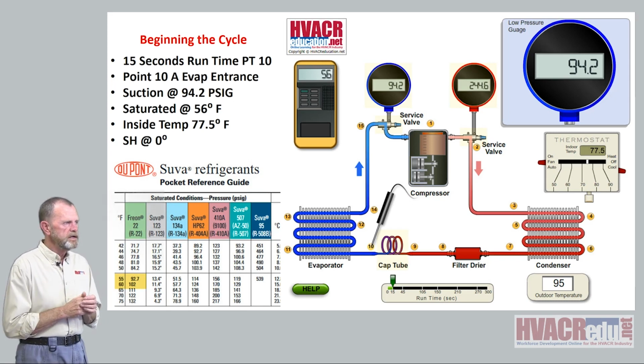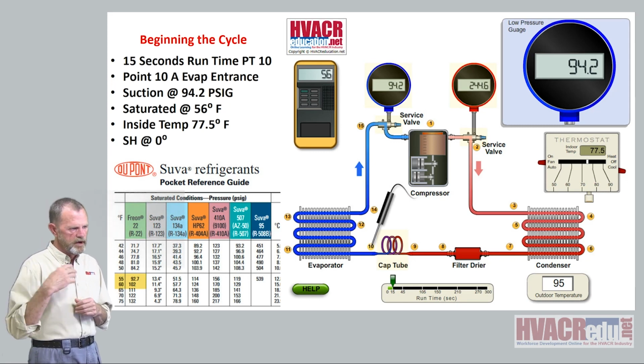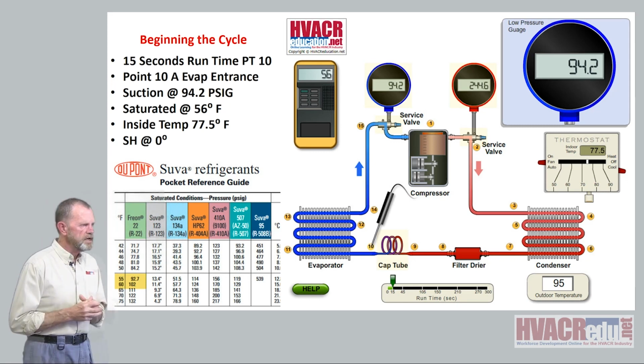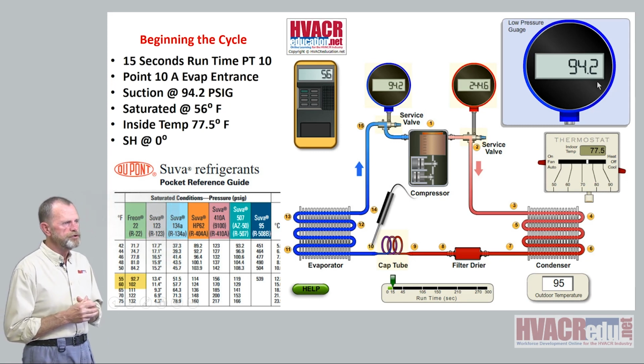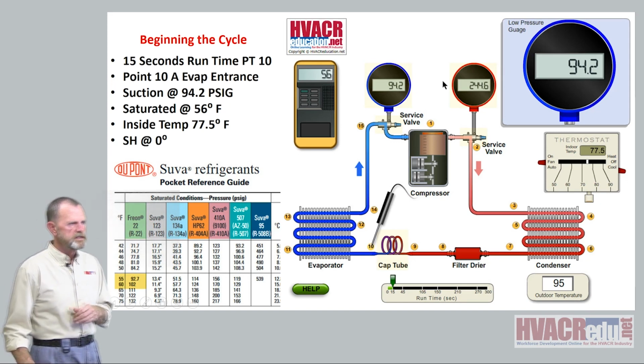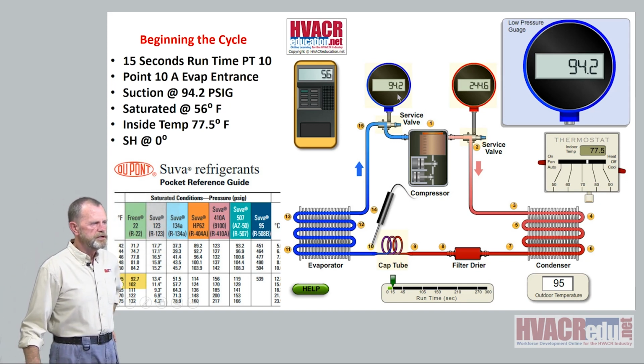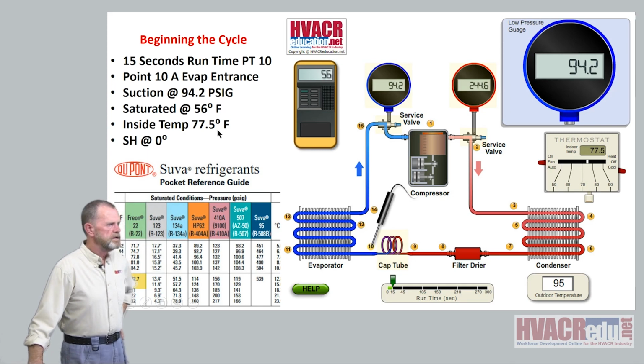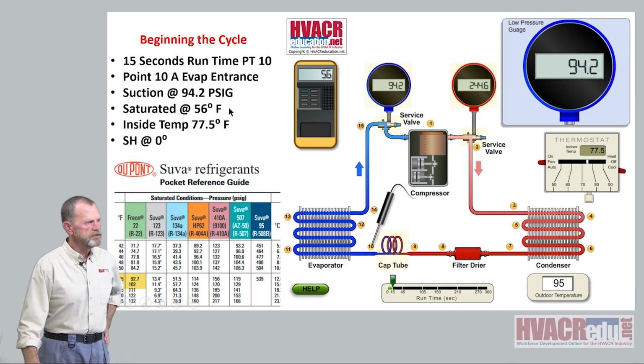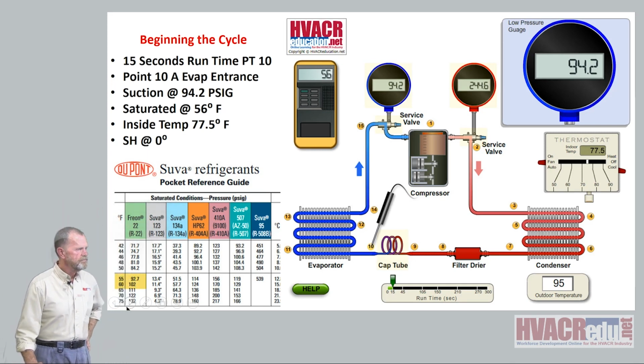We're at point 10. We're 15 seconds into the run. We have the highest level of the load. Suction is at 94.2 right here. You can see it in the big window, and you can also see it here in the suction gauge. Saturated temperature is 56 degrees. If you look down here, I've got the pressure temperature chart shown on the screen. 94.2 PSIG is somewhere around 56 degrees.